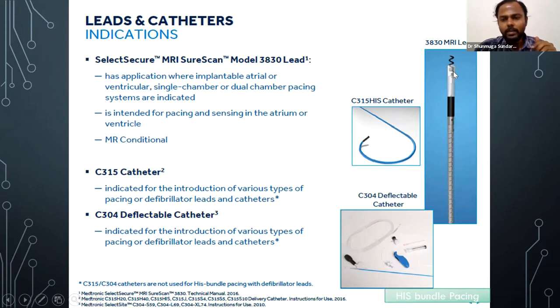It's an open helix lead, 4.1 French. It has an open helix - this is the cathode, around 1.8 millimeters, and this is the anode. The inter-electrode distance is 9 millimeters. If you measure from the end of the anode to the tip of the lead, it corresponds to 10.8 millimeters.